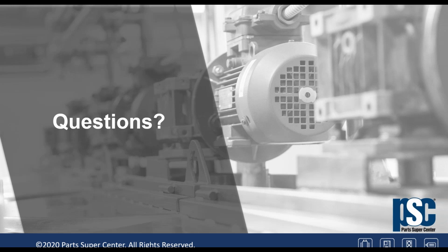Our first question is, approximately when did OSHA change the standards on fan guards? How old of a fan unit would be a concern of not meeting current OSHA standards? Again, in the late 70s, only because there were a lot of incidents of people, willingly or not, getting hurt, and OSHA said we have to make it so that you cannot. It was the middle 70s, and OSHA also said that if they are not OSHA guards, they have to be at least 6 feet above the ground level, because usually at 6 feet or above, people can't put their hands in where they shouldn't. So again, the answer is the middle 70s.